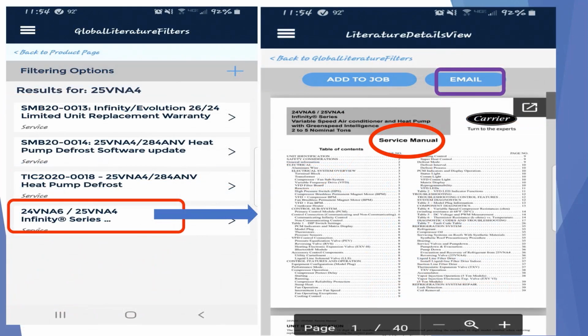When we have selected all literature, as I said, everything that is available for this unit will be brought up, as well as bulletins that will give us certain information regarding any reworks or any issues that have come up with this unit. We have chosen to bring up the service manual, which is what we will need to do technical work. It has all the service information: ohms on the compressor, resistance of all the sensors, voltages, volts DC that we should be seeing on the system.